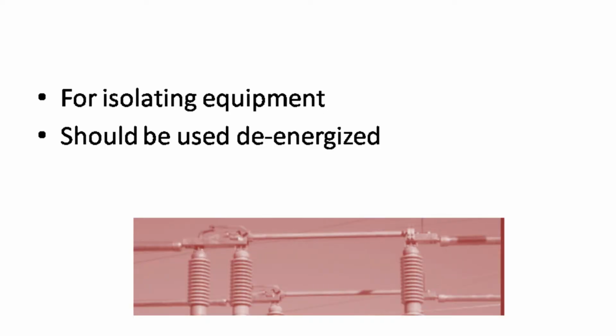A disconnect switch is used to make sure a circuit is completely de-energized. In substations, the disconnect switch is for isolating equipment such as transformers and breakers so that crews can safely maintain them. Now, even though some switch disconnects have arc extinguishing capabilities, these are not used for breaking a live circuit, mainly to be opened when de-energized. We will leave the breaking of the circuit to the hands of the circuit breaker.